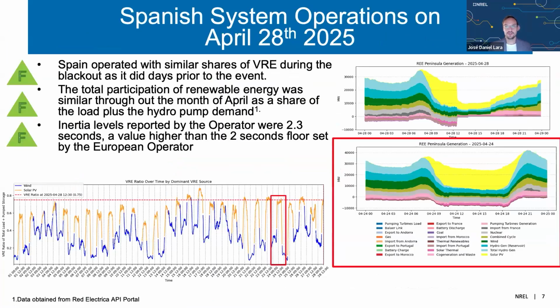So what was the operational situation in Spain? Generally, by the time the event happened in this red window, the penetration of renewables with respect to total load, taking into account the load produced by hydro pump, was about 75%. As you can see from the days prior to the blackout, and even some days afterwards, this level of renewable penetration is not abnormal. Spain had operated with similar shares of variable renewable generation during that blackout and in the days prior to the event, and the total participation was similar through the month of April.